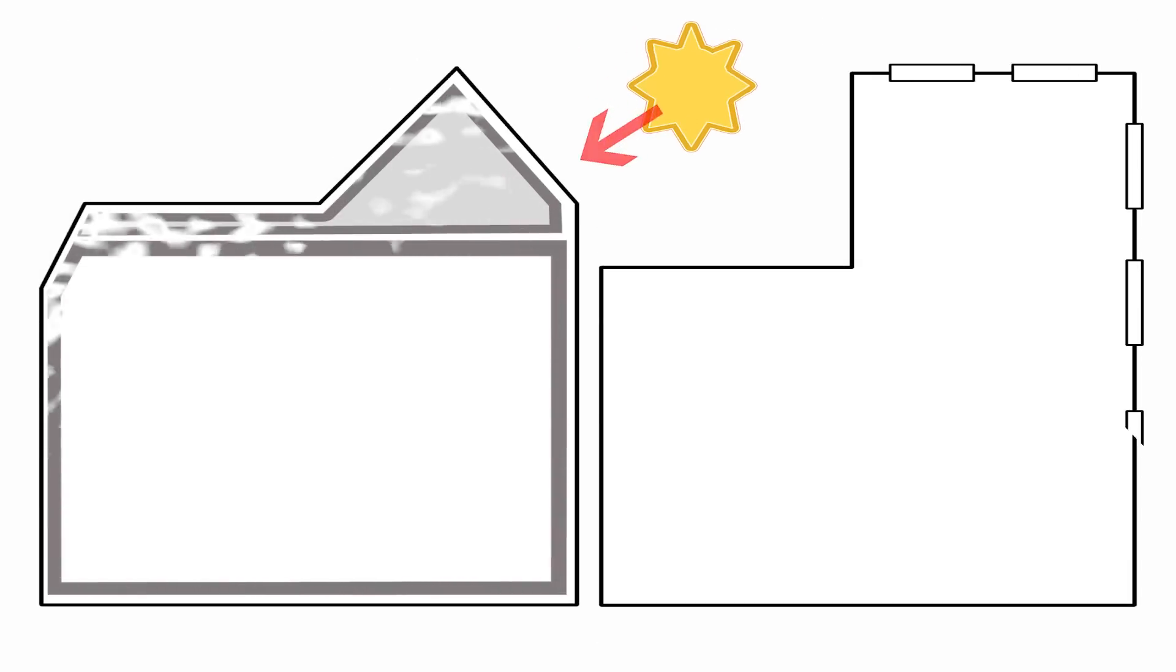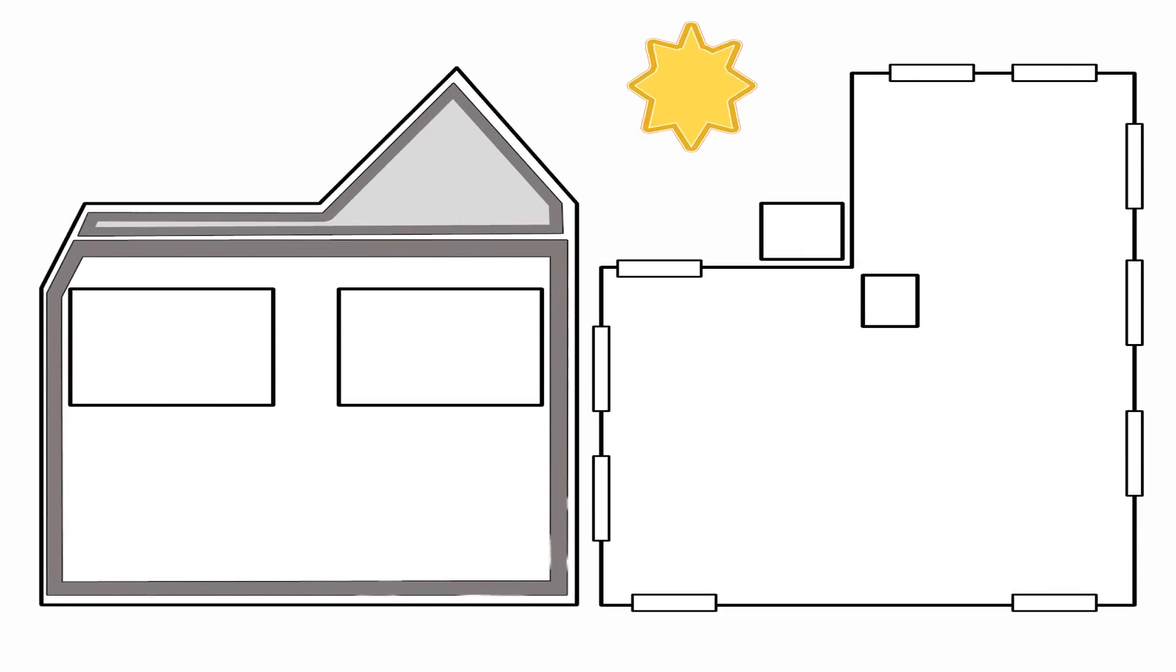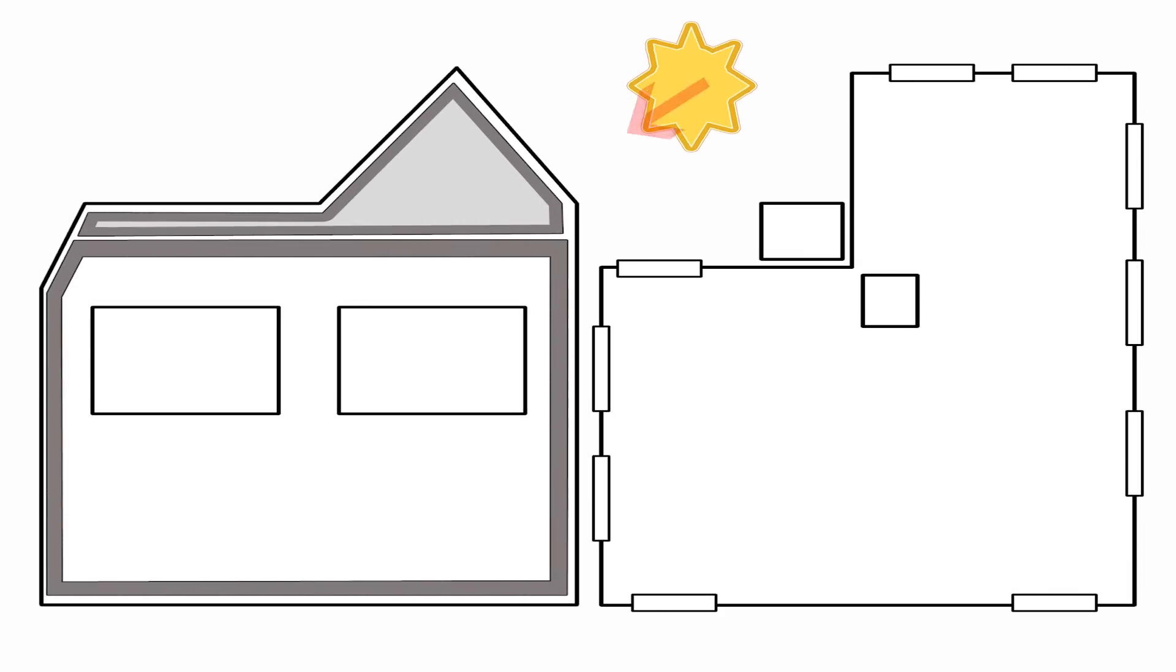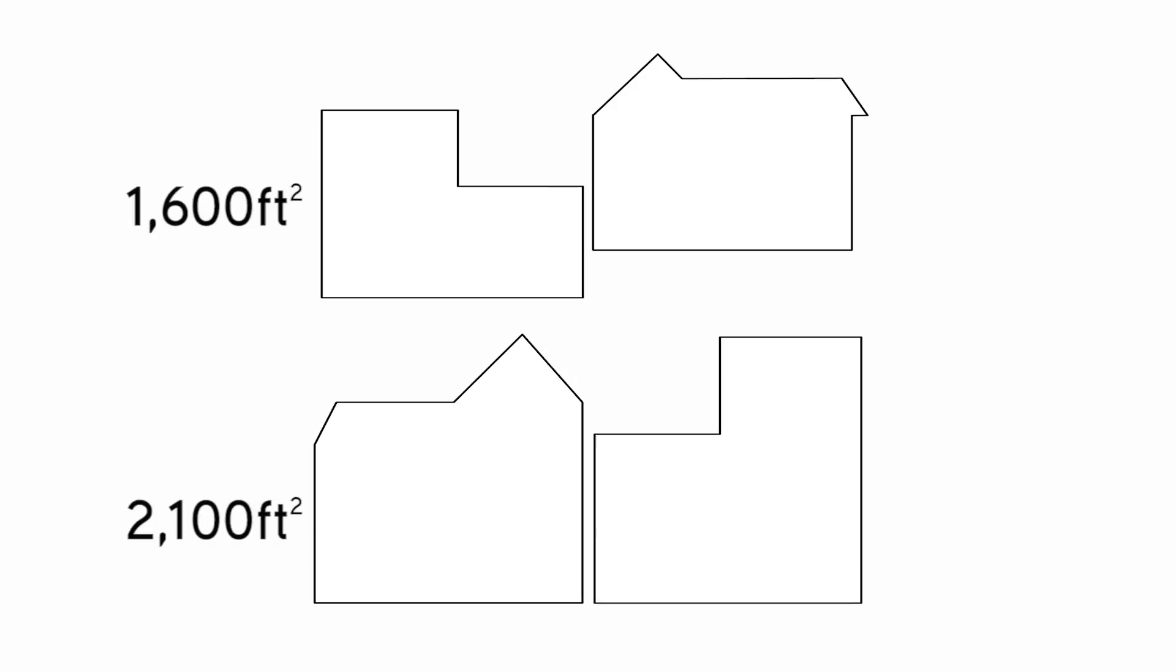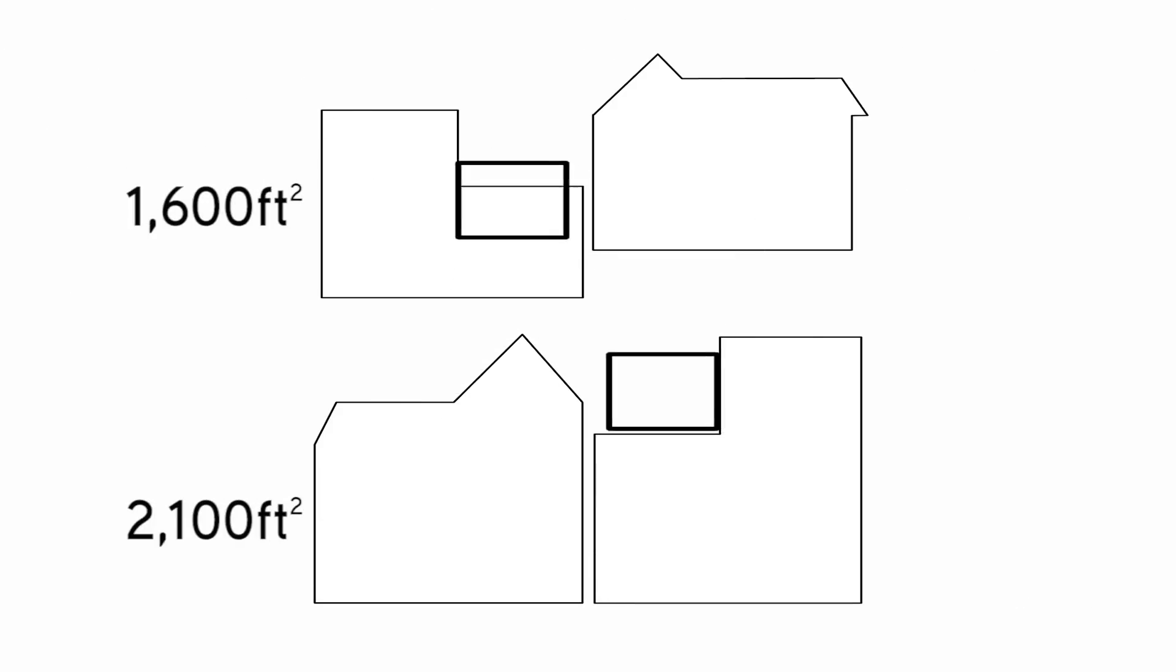But on the 2100 square foot home, you have R36 insulation, less window space, meaning less heat gain, and better insulation in the walls. While the square footage varies in both homes, they can use the same size system because the larger home is more energy efficient.